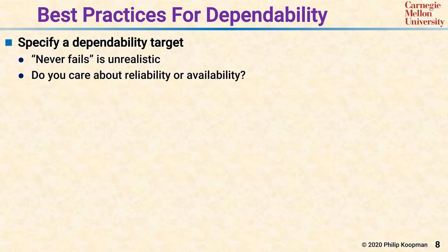If you have a continuous operation system but you care about reliability, what you need to do is break that continuous operation into a set of missions so that you are able to, for example, switch between a primary and a backup once a day so you can do diagnosis and repair on the backup and then restart its mission clock the next day. It's important to minimize the impact of a fault on the system.